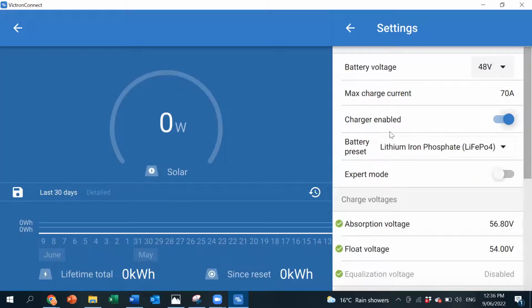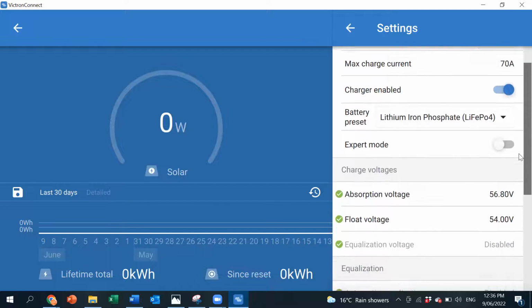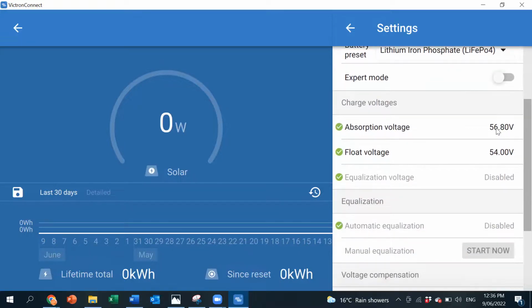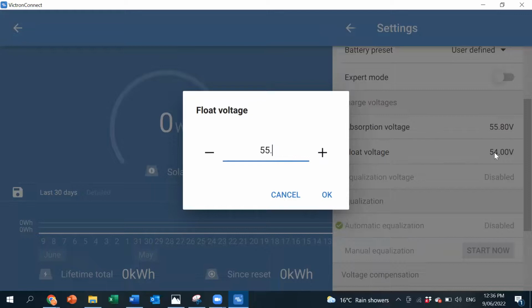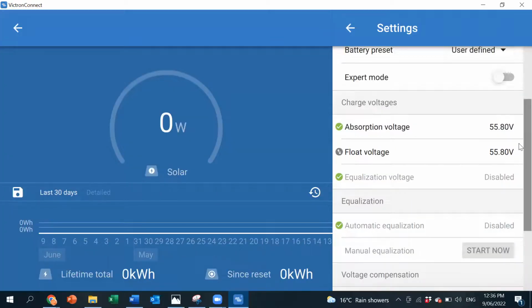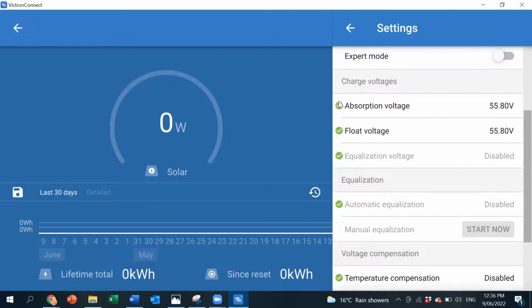Now I've set it to lithium iron phosphate, and you see the voltages are too high for us. So I need to pull that back to 55.8 absorb voltage and 55.8 float, which suits the Freedom 1 batteries. See the little green tick on the left-hand side? That shows you the charge controller has accepted that program.